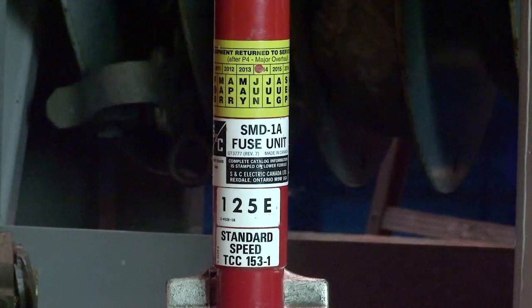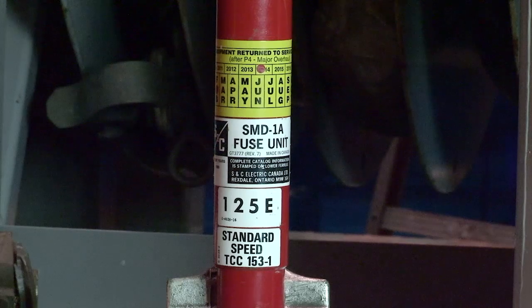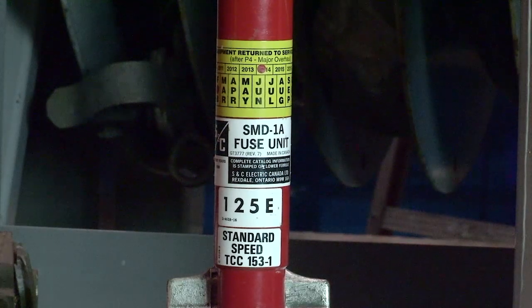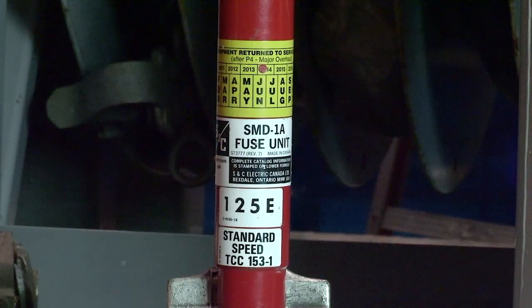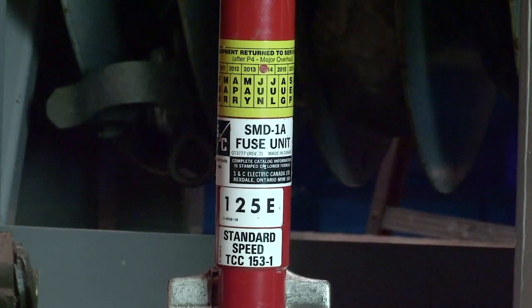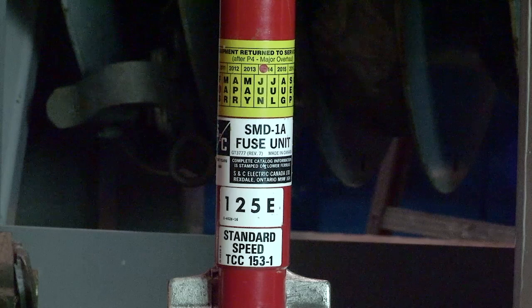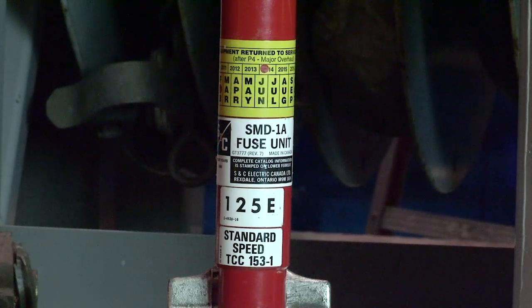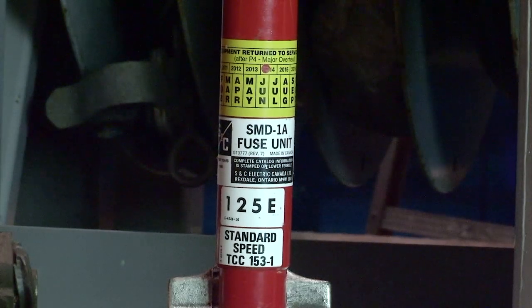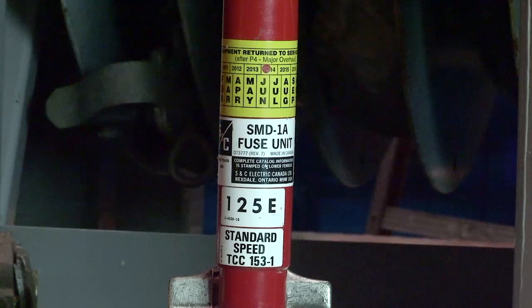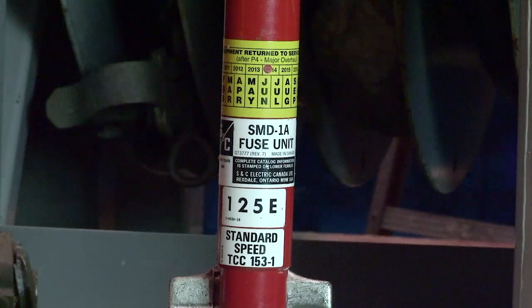Now the 125, every DS could be different. Some might have 150 amps, 125 amps. Some might even be 200 amps. Typically, the higher the fault amps at the DS, the higher the fuse rating we'll need to put in. So for 125, you could have maybe 3,000 fault amps at the DS, and a 200 amp fuse may have 5,000 fault amps at the DS.